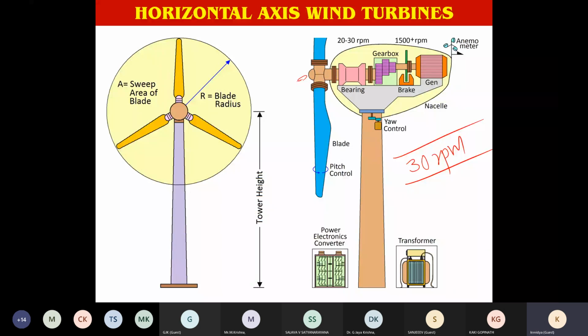In NTPC, we have a 2 megawatt wind turbine. Its speed is just 15 RPM. And at 15 RPM, for generating 50 Hertz, we need 400 poles. It is practically impossible to make a generator with 400 poles standing at a height of about 120 meters. So, to reduce the size of the generator, the easiest method is to put in a gearbox, and that is why almost 80 to 90% of the commercially running wind turbines have a gearbox. Of course, you can have gearless wind turbines as well, but they will be very bulky.